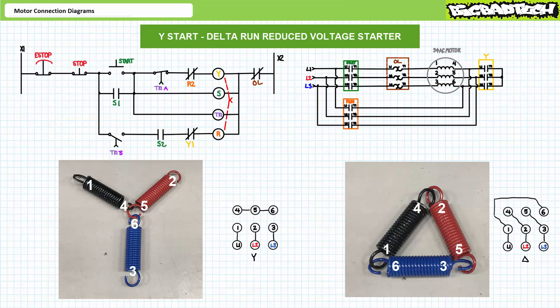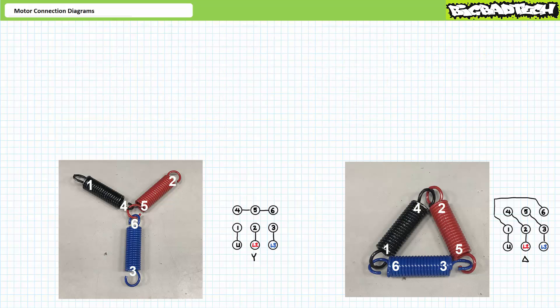We'll examine Y-start delta-run reduced-voltage starters in greater detail in later lectures. This is not art class and you get zero points for creativity. Follow the connection diagrams exactly as illustrated, otherwise you might damage the motor, your equipment, or yourself. As presently illustrated, a Y-configured six-lead motor ties together leads 4, 5, and 6, and the delta configuration goes 1, 4, 2, 5, 3, 6 when traveled in a clockwise fashion.